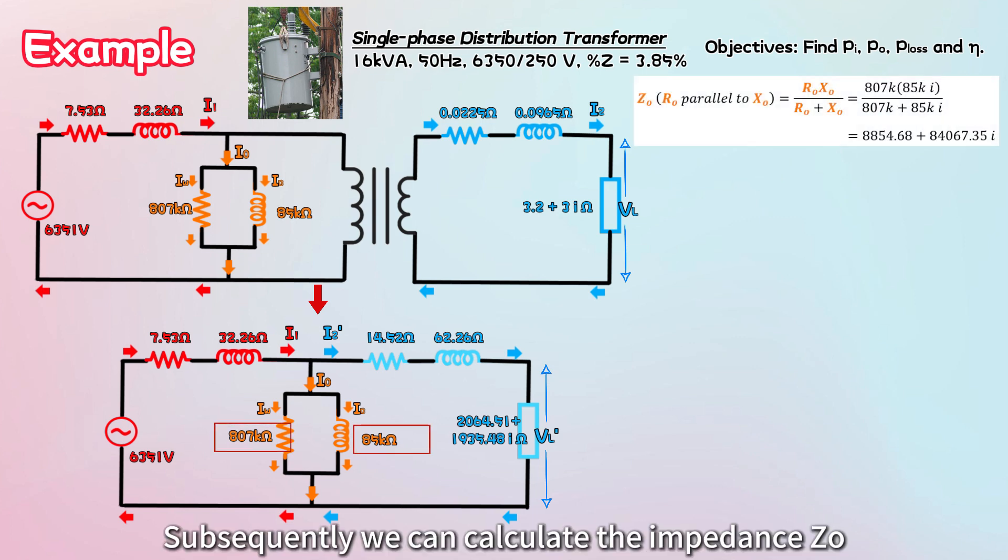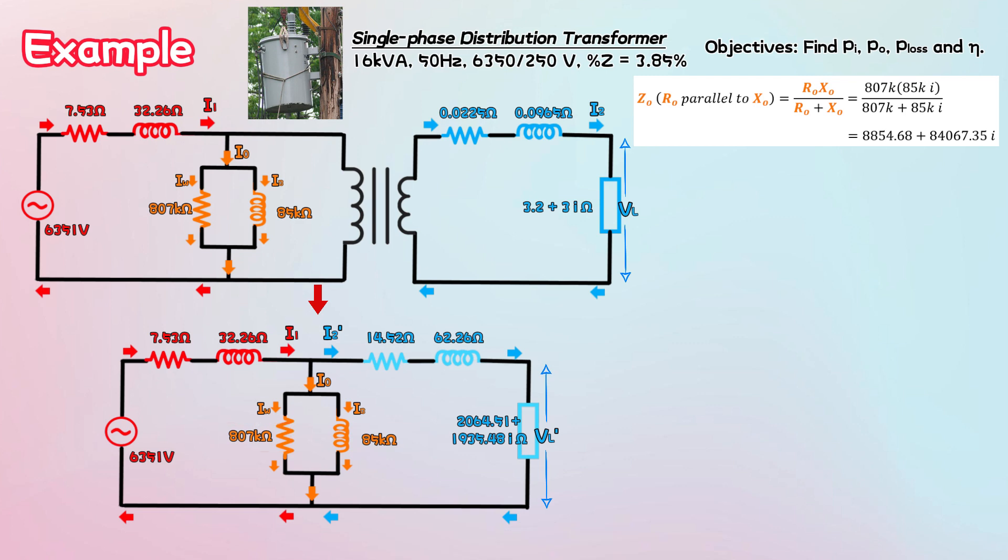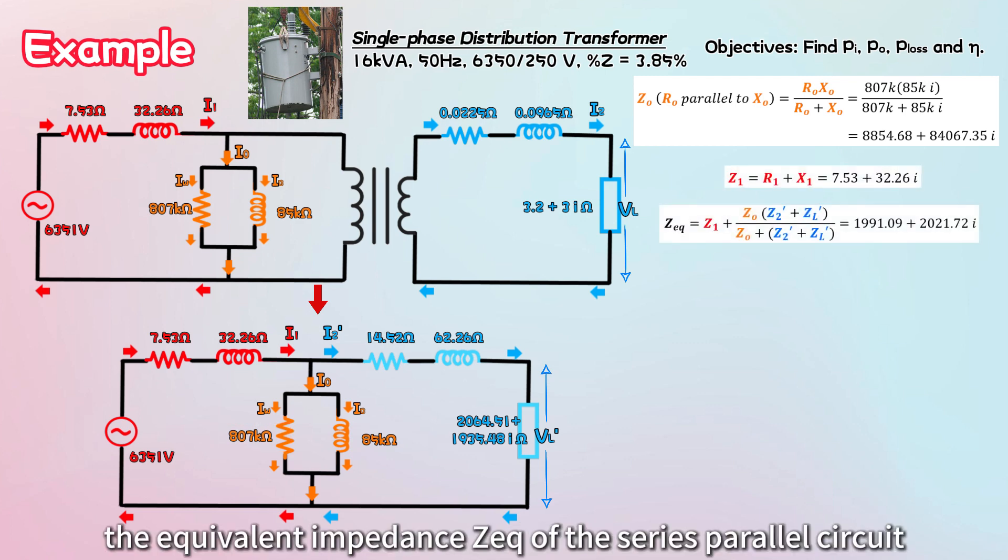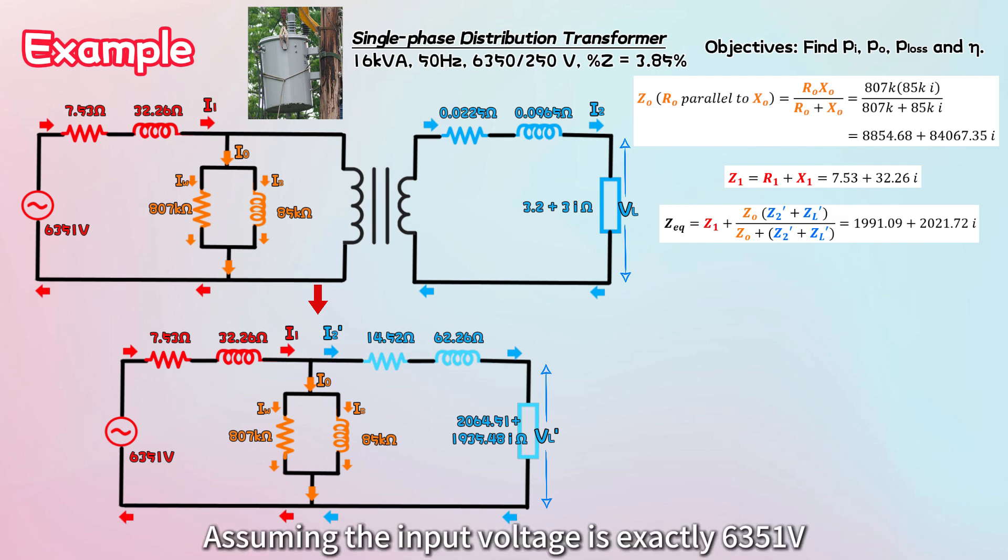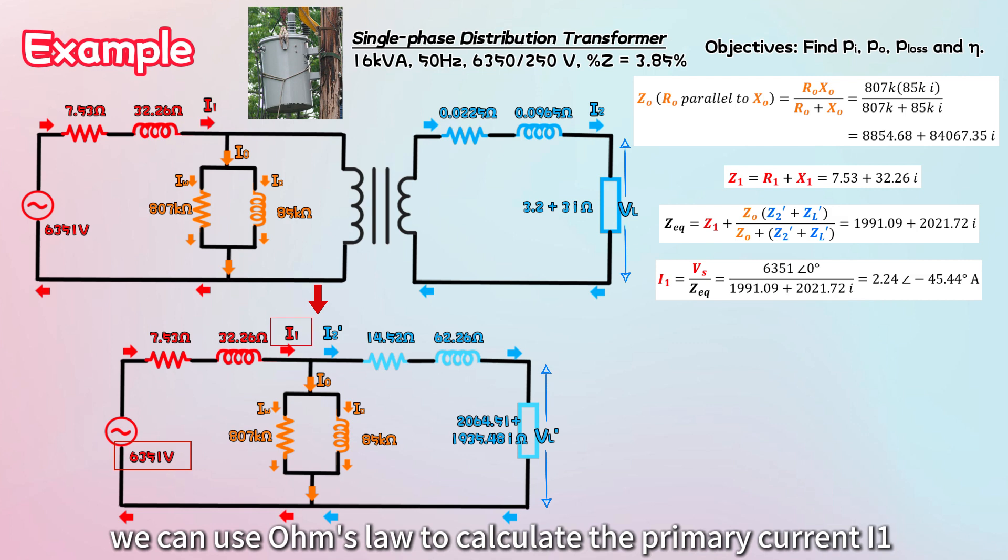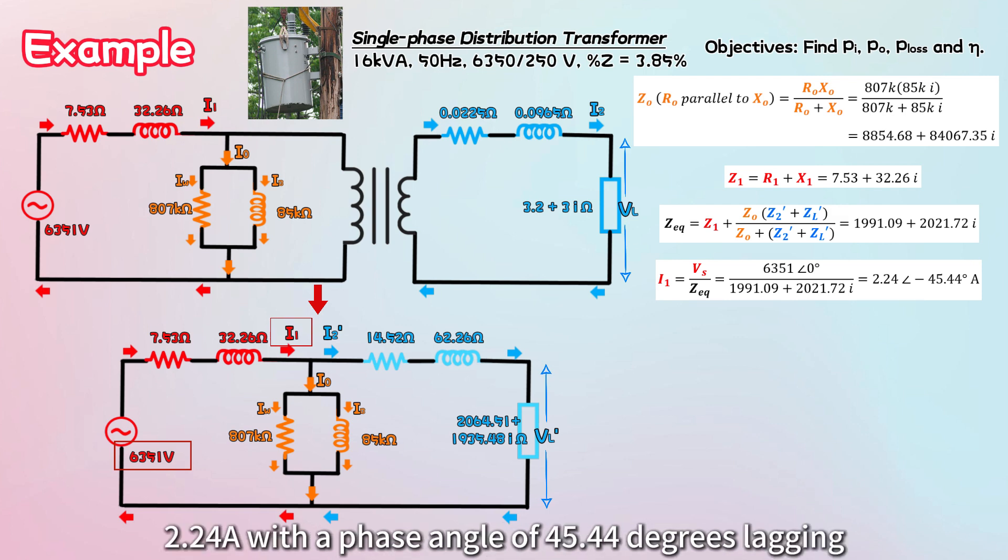Subsequently, we can calculate the impedance Z0 of R0 parallel to X0. Once we've done this, we can find the equivalent impedance of the series parallel circuit. Assuming the input voltage is exactly 6351 volts, we can use Ohm's law to calculate the primary current I1. The resulting primary current is 2.24 amps, with a phase angle of 45.44 degrees lagging.